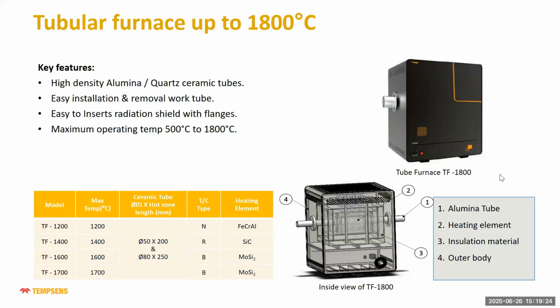We have different models available. The TF 1200 works up to 1200 degrees centigrade, using an N-type thermocouple and FeCrAl heating element. Then the TF 1400 has an R-type thermocouple and a silicon carbide heating element. The TF 1600 uses a B-type thermocouple and a molybdenum disilicide heating element, and the TF 1700 uses a B-type thermocouple and MoSi2.